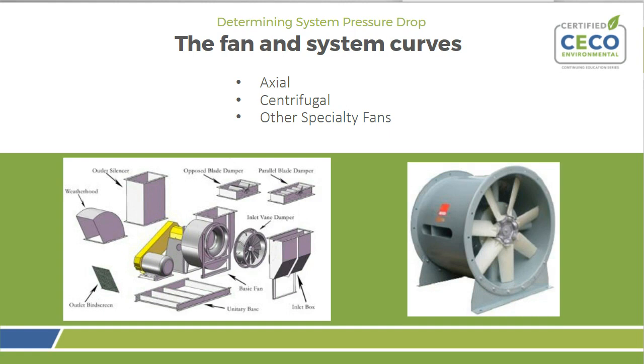Fan wheels: if it's on the clean side of the dust collector, backward inclined is the way to go. The only time you can't do that is if the static pressure is high enough, you'll have a radial blade wheel, paddle blade wheel. And if the fan is on the dirty side of the system or the collector, you almost always go with a radial wheel blade.